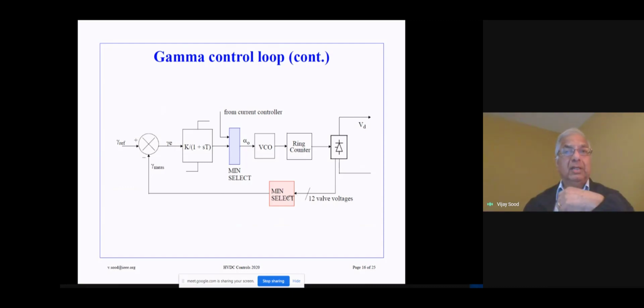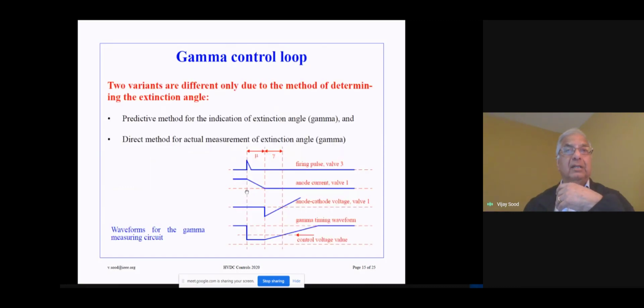And in order to measure the gamma, the valve voltages are required. And this is a variation of how we can generate the value for the gamma measurement circuit. There are two variations. One is the predictive method of control for gamma. The second is a direct method for the actual measurement of extinction angle. Different manufacturers have proposed different techniques.